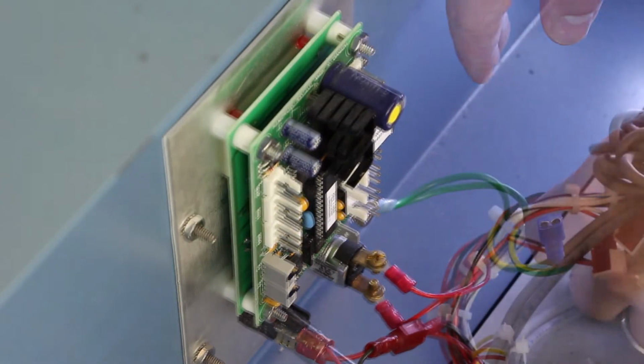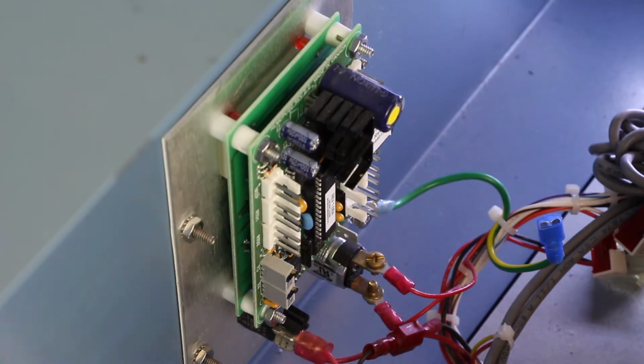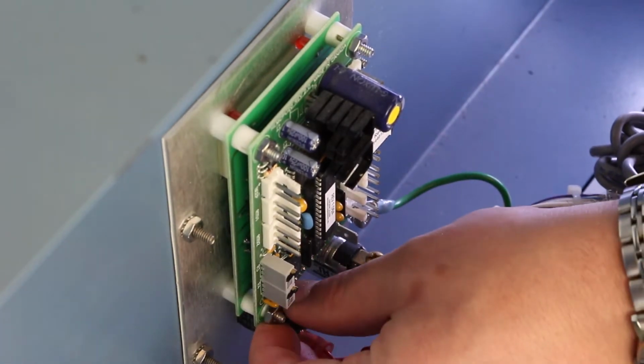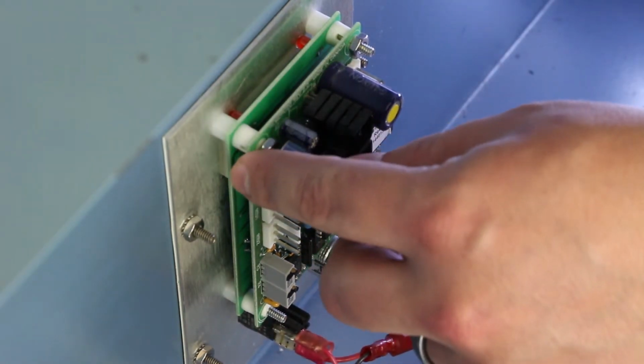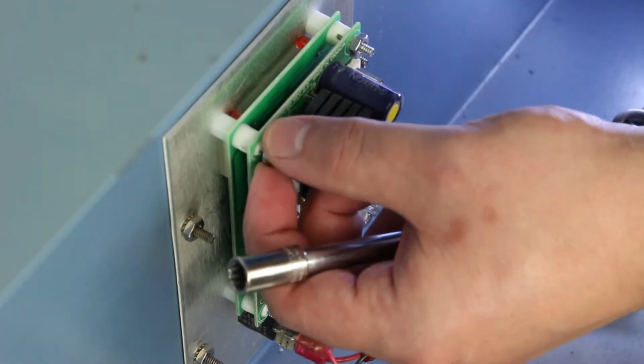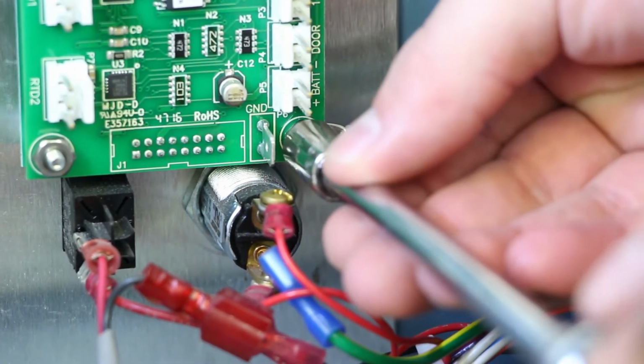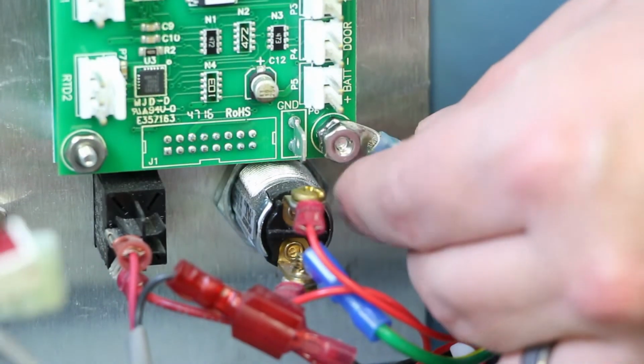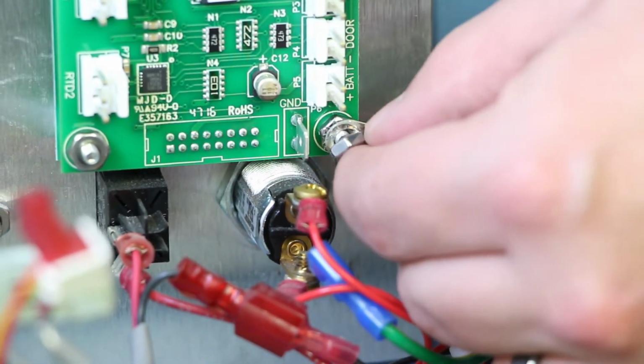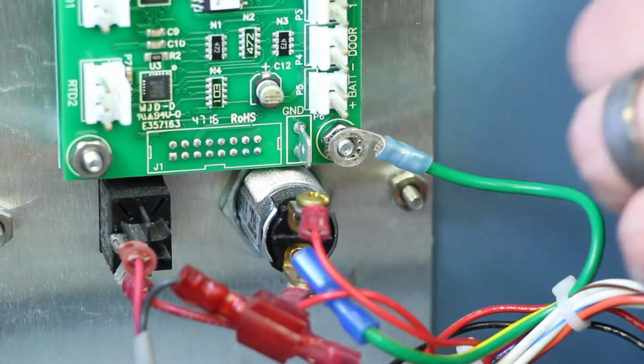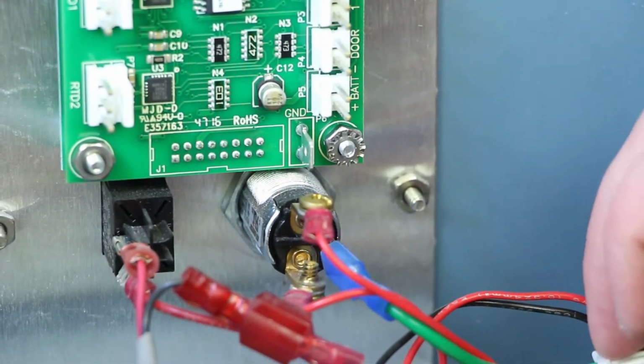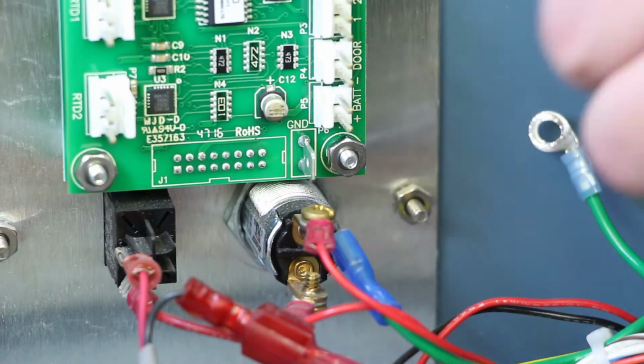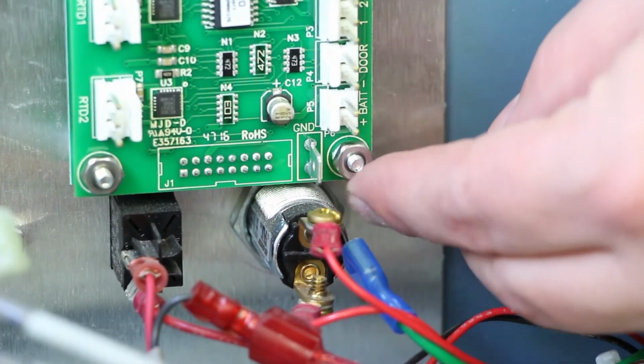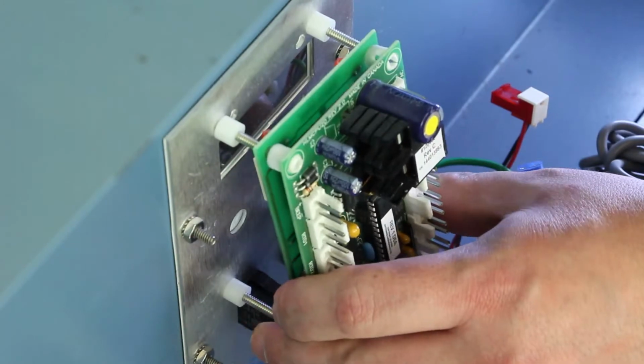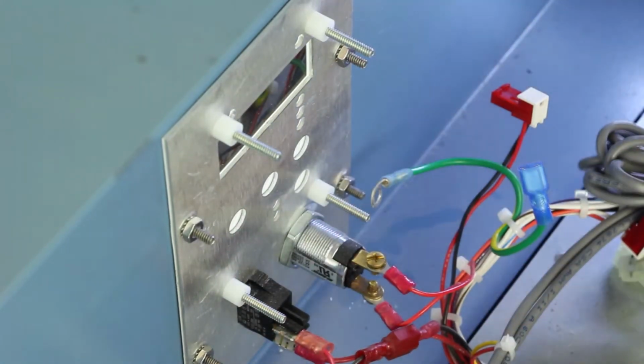Next, loosen the nuts on the four corners of the board that hold it in place. A 5/16 socket can be used to remove the nuts. The ground wire post has one nut to hold the board and a second to attach the wire. With the nuts and wires removed, the circuit board can be removed and a new one slid into place.